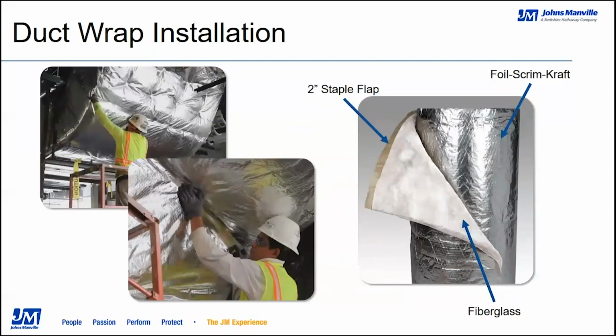The installed R value of duct wrap is based on the installation of the product over sealed sheet metal ductwork with the average installed thickness at 75% of the product's nominal thickness. That means no more than 25% compression on the fiberglass, because as you compress fiberglass, you reduce your thermals, or your R value. You should make sure that you cut the wrap to the proper stretch-out dimensions. Those stretch-out dimensions can be found on our website at jm.com on our product data page, as well as on every individual bag of duct wrap that we send out. We have the stretch-out and layout chart for what you need dimension-wise for your duct wrap.